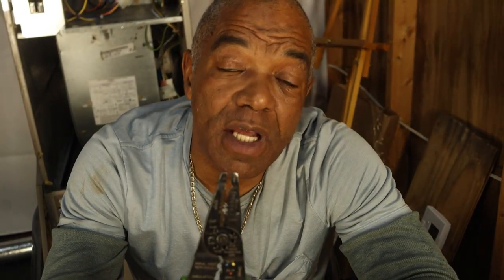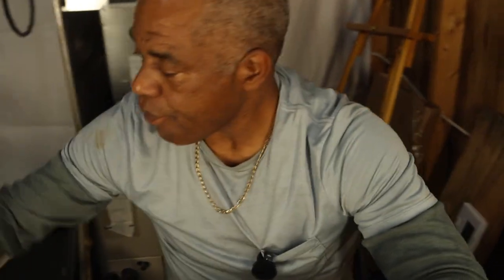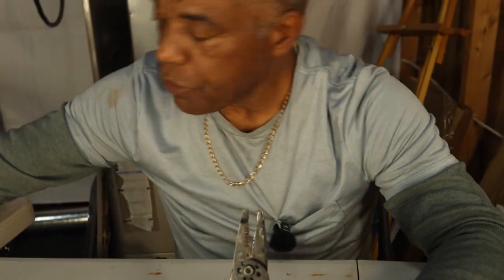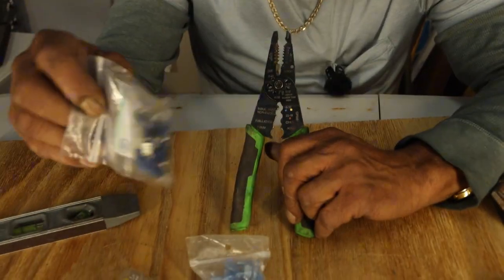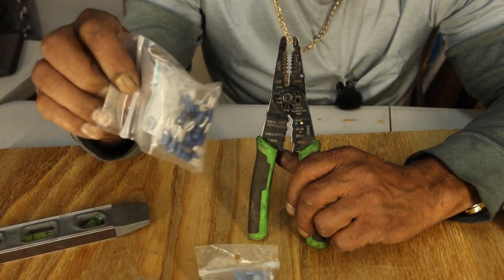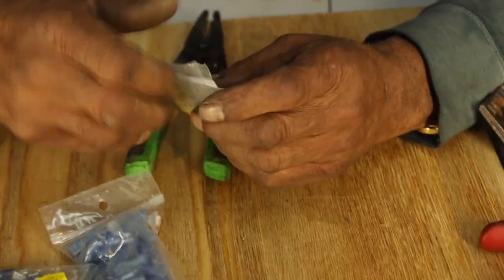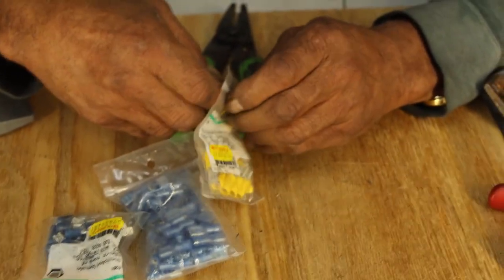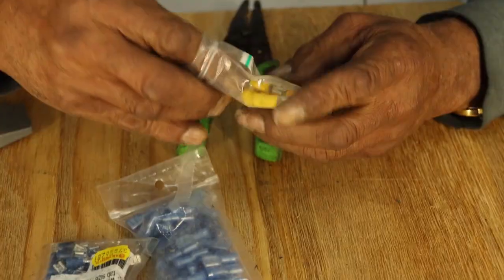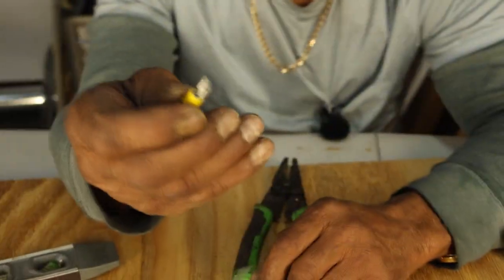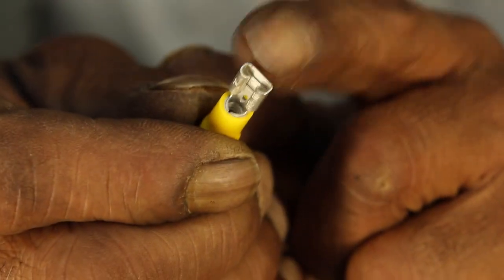We have to strip our thermostat wires. We have to strip our line voltage wire. Sometimes we have to repair wires, put new wire spades on. A wire spade, that's these. For different systems, different applications, you have to connect to the system with spades that fit onto certain plugs in the unit.